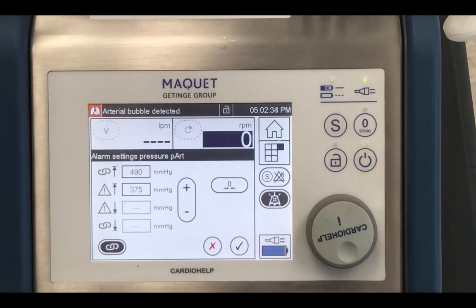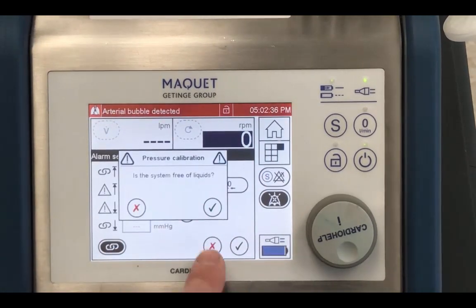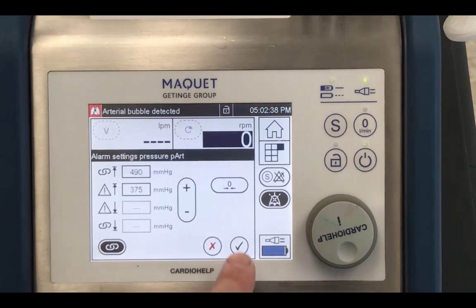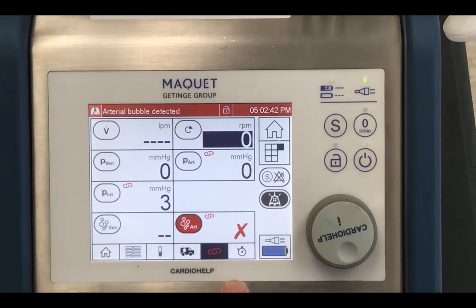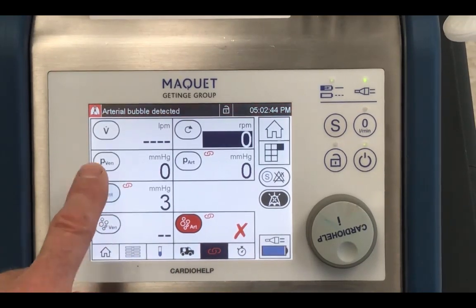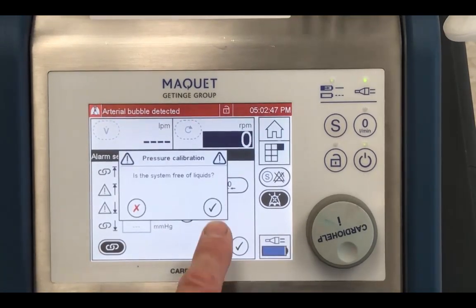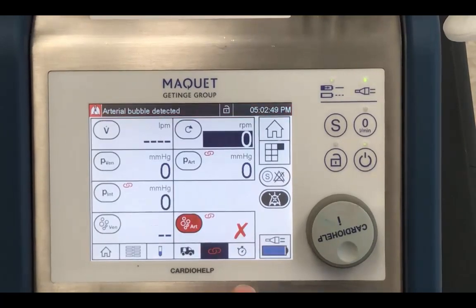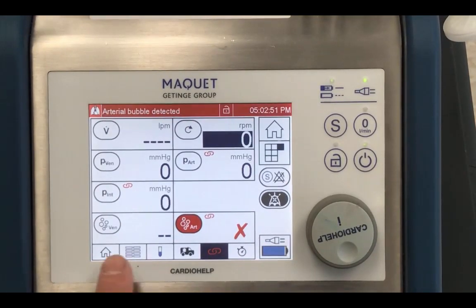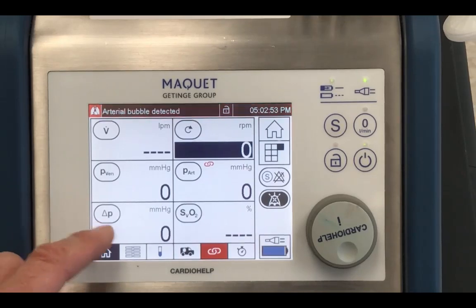Let's zero that one. Touch that. Is free from fluids. Yes, it is. Now it's going to set to 0. We enter that. Calibration. Good. P internal. Zero it. Accept it. And if we go back to the home screen, we're going to see the delta P is 0.